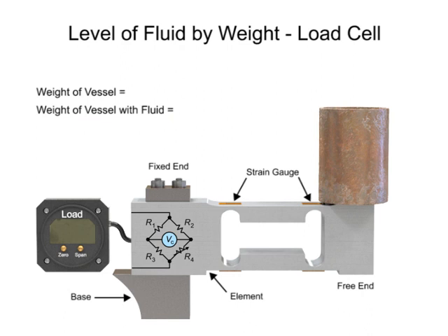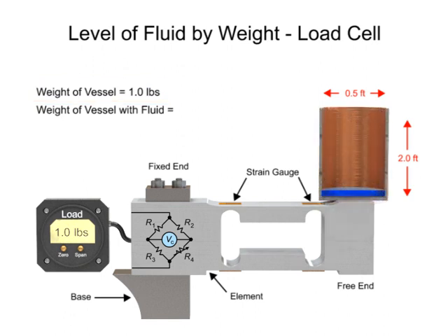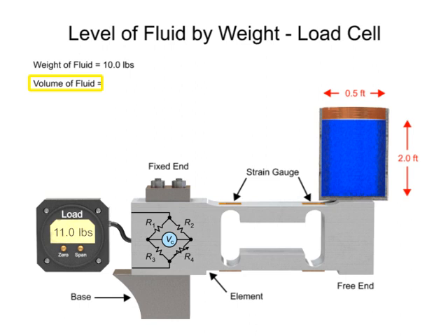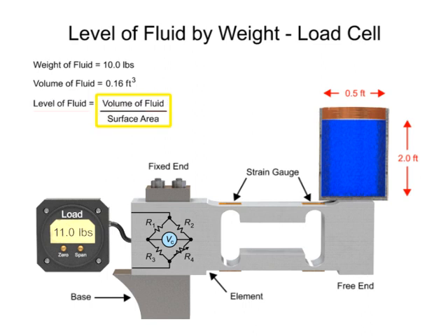As an example, to determine the level measurement of a column of water that is 2 feet tall with a diameter of 0.5 feet, the first step is measuring the weight of the vessel. The weight of the fluid is determined by subtracting the weight of the vessel from the weight of the vessel with fluid. The volume of the fluid is then derived by dividing the fluid weight by the density of the fluid. The level of the fluid is finally calculated by dividing the volume of the fluid by the surface area.